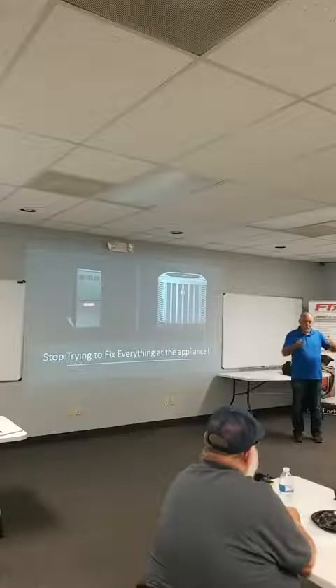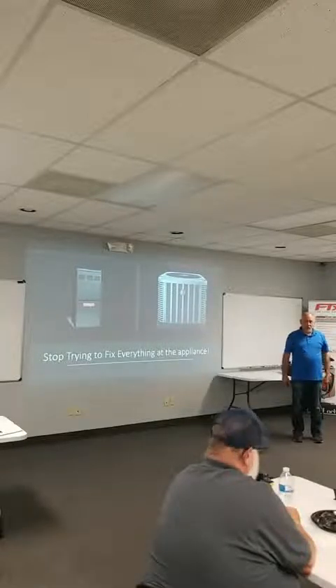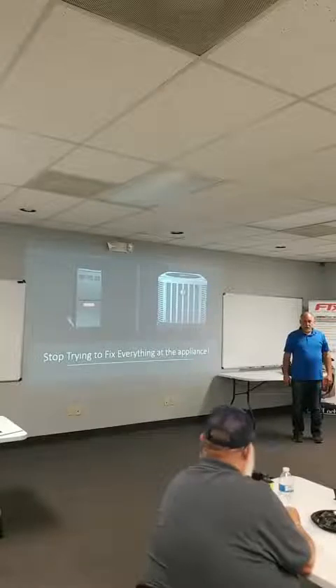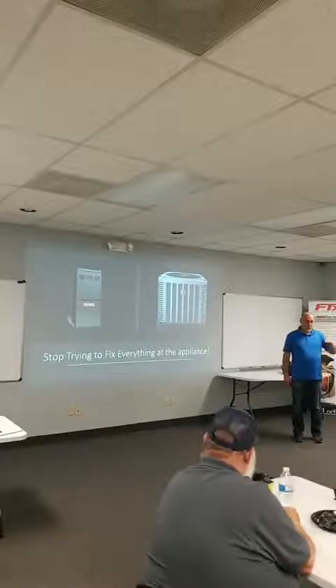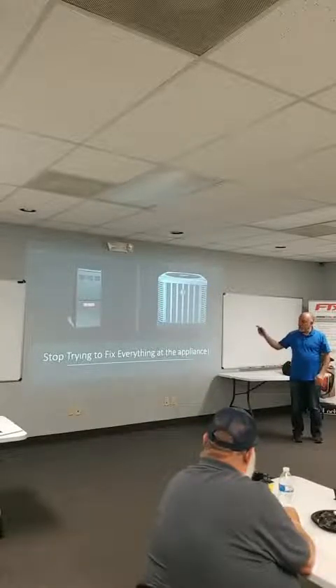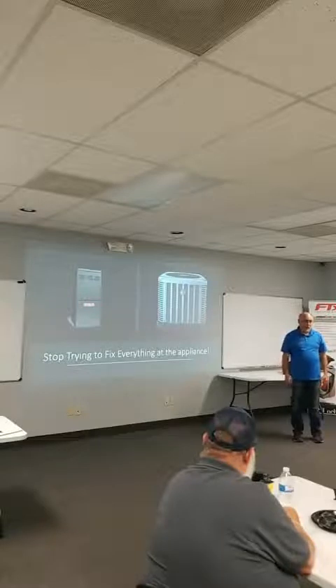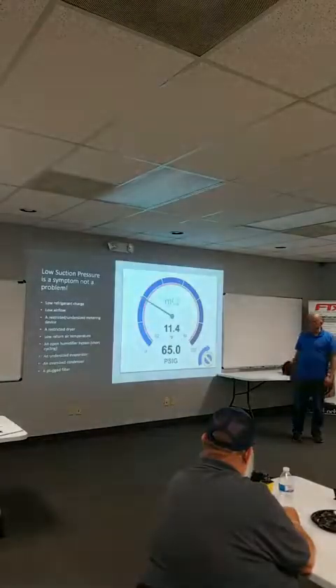The main problem with the system was there's no inlet guide vanes. We had high static pressure in the ductwork. We had excessive amounts of airflow. It's blowing apart the ducts. It's totally pressurizing the building wrong, right? And this is the kind of stuff that, if you start taking a system approach instead of trying to fix everything at the appliance, will absolutely change the way you do work. Because it's not the appliances that have problems as much as it is the systems, right?